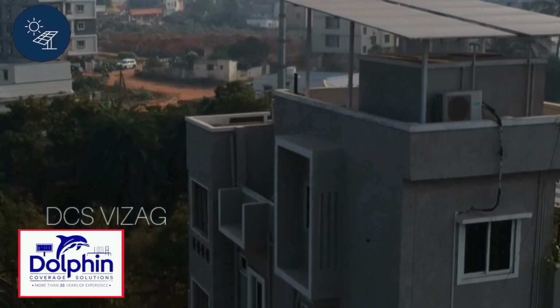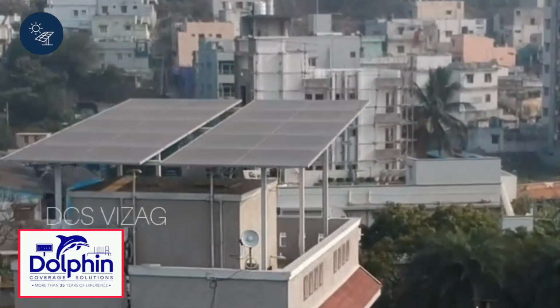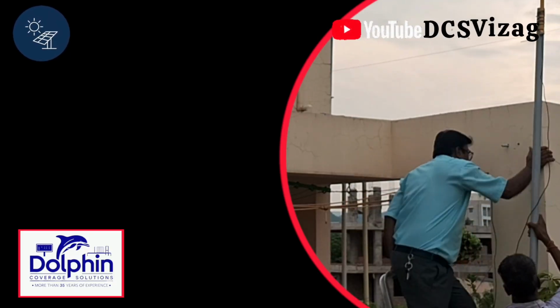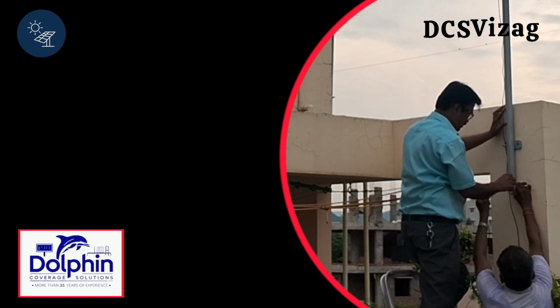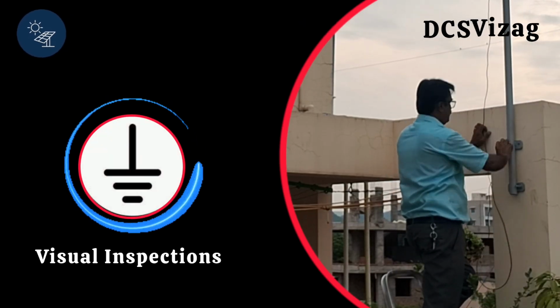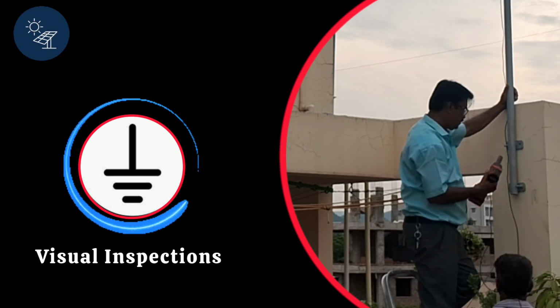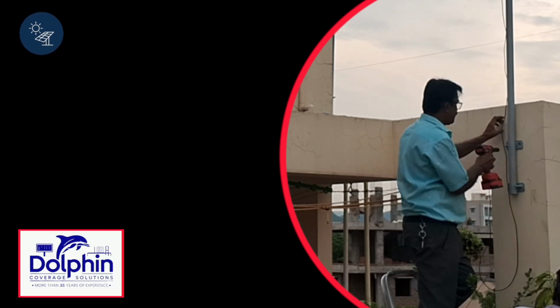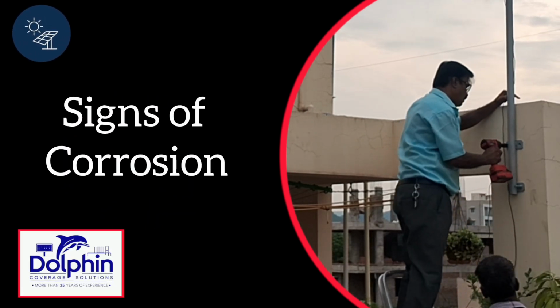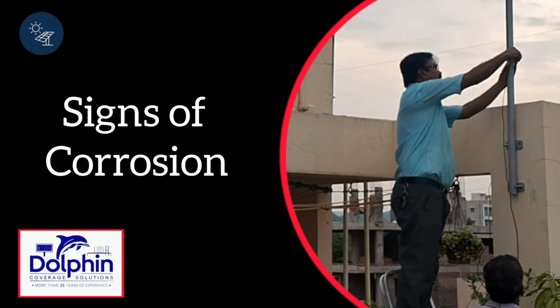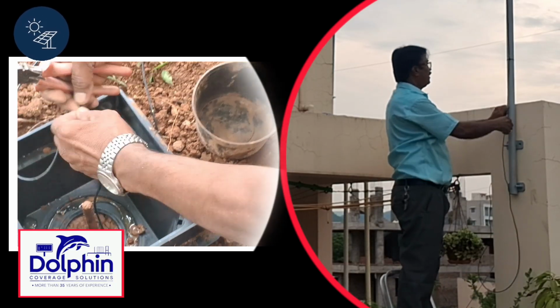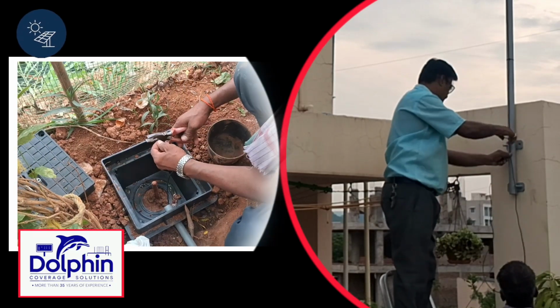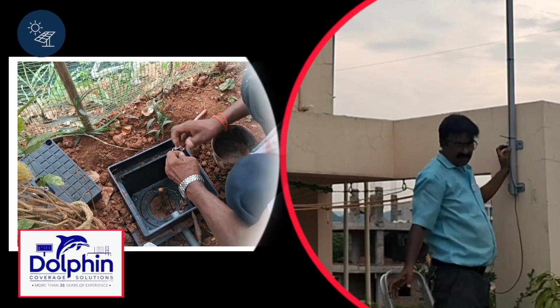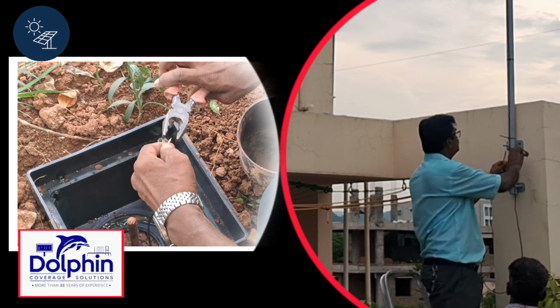Maintain detailed records of the earthing system, installation, and test results. This is vital for future maintenance and compliance checks. Conduct visual inspections of all earthing components at least once a year, more frequently in corrosive environments, for signs of corrosion, damage, or loose connections. Any identified issues like broken conductors, corroded terminals, or high earth resistance values should be addressed immediately by a qualified electrician.